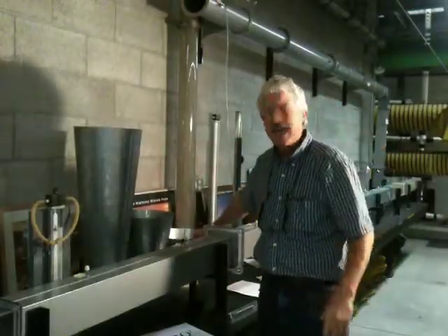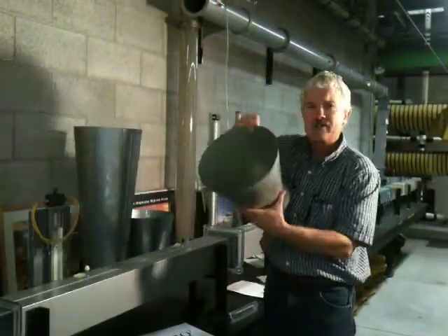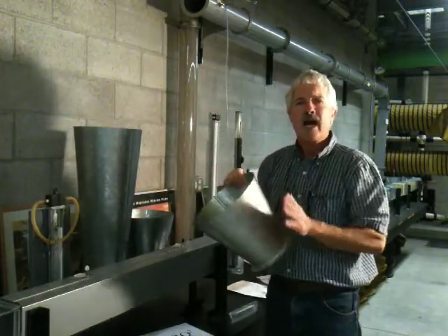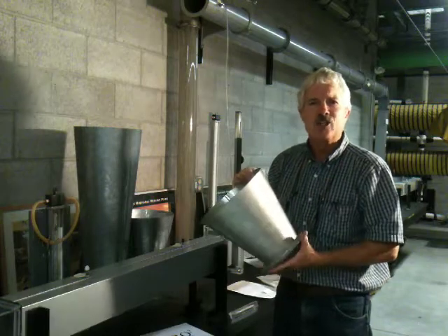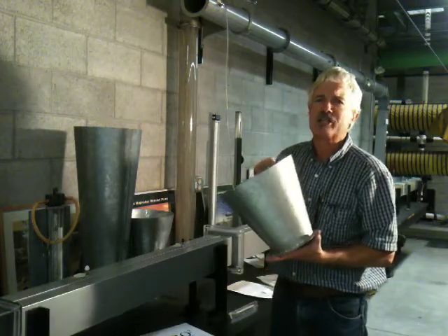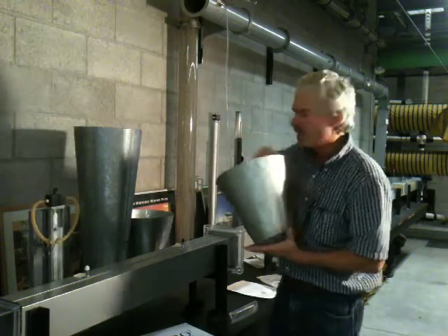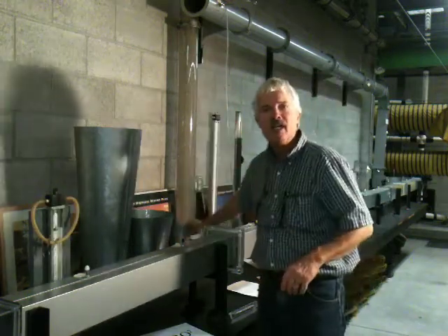And you might think that the discharge of a duct of an airway is that. The air is exiting and that's that. But it actually turns out that if you use an évasé, you're actually guiding the air as the flow area is increasing, and you're reducing the shock loss of the air mixing at high velocities with the air in the local environment. And you can actually dramatically improve the performance of an airway with an évasé. So that will be the last exercise that we'll study.